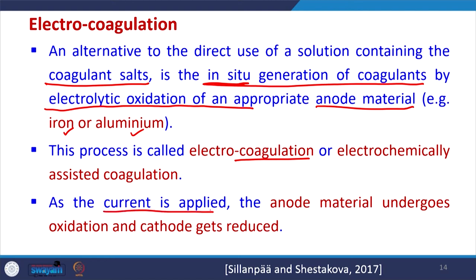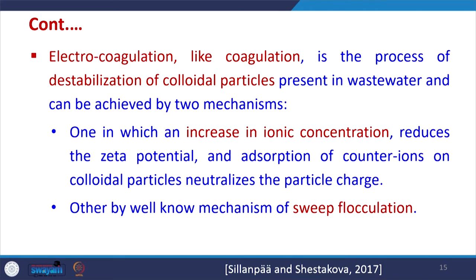As current is applied, the anode material undergoes oxidation and the cathode gets reduced. Electrocoagulation, like conventional coagulation, works by destabilizing the colloidal particles present in the water. Colloidal particles that are not able to settle down can be destabilized: their charge gets reduced. If enough mixing is provided, different colloidal particles come together and form flocs which then settle down. Using the in-situ generated coagulants, the colloidal particles are destabilized in the water.